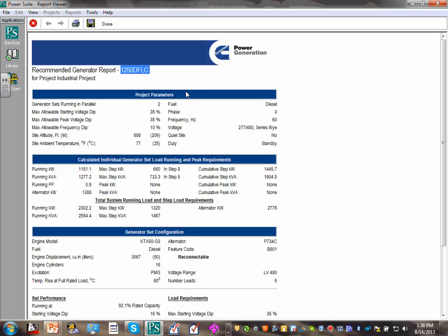Did they say 250? Yeah. I'm sorry, 1250. I apologize. Sounds like it for 4,000 amp. No, I apologize, 1250. Yeah, 1,250 kW. These are 1,250 kW. That's a big boy. So two of them will cover a 4,000 amp switchgear.